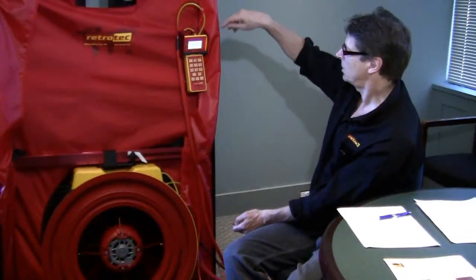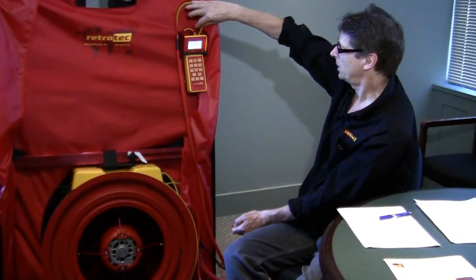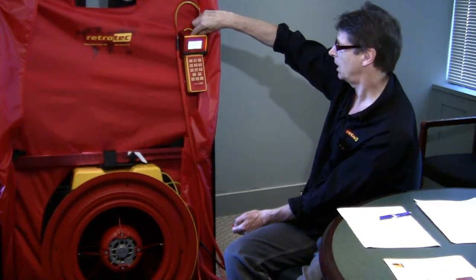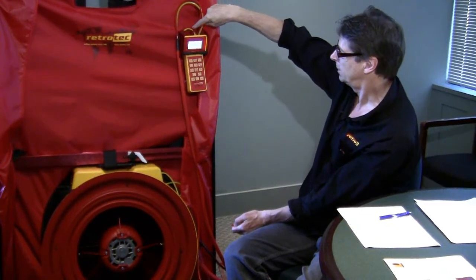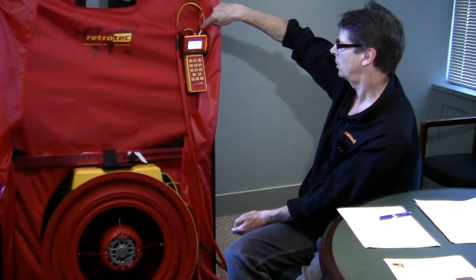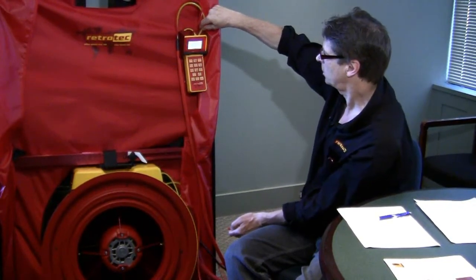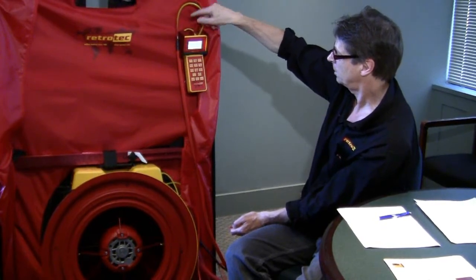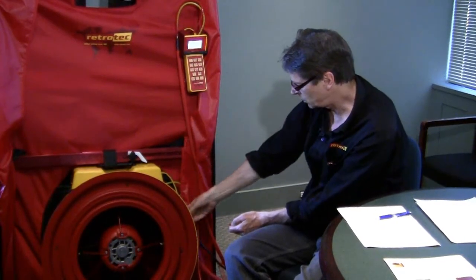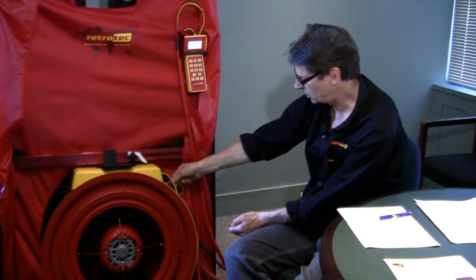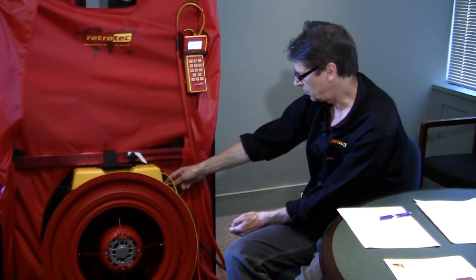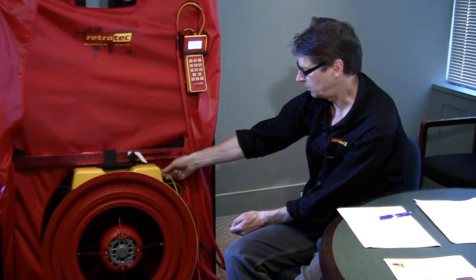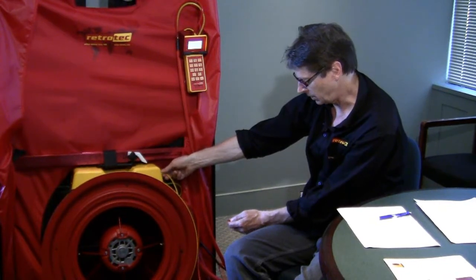The gauge setup consists of the red tube and yellow tube being connected to the red and yellow ports on the gauge, in this particular case for building pressure and for fan pressure, and a yellow Ethernet cable which comes out, which is a control cable. This comes down over towards the fan, and the yellow connector goes into the fan onto the reference B port. And the Ethernet cable, which is the controlling cable, goes into the fan.